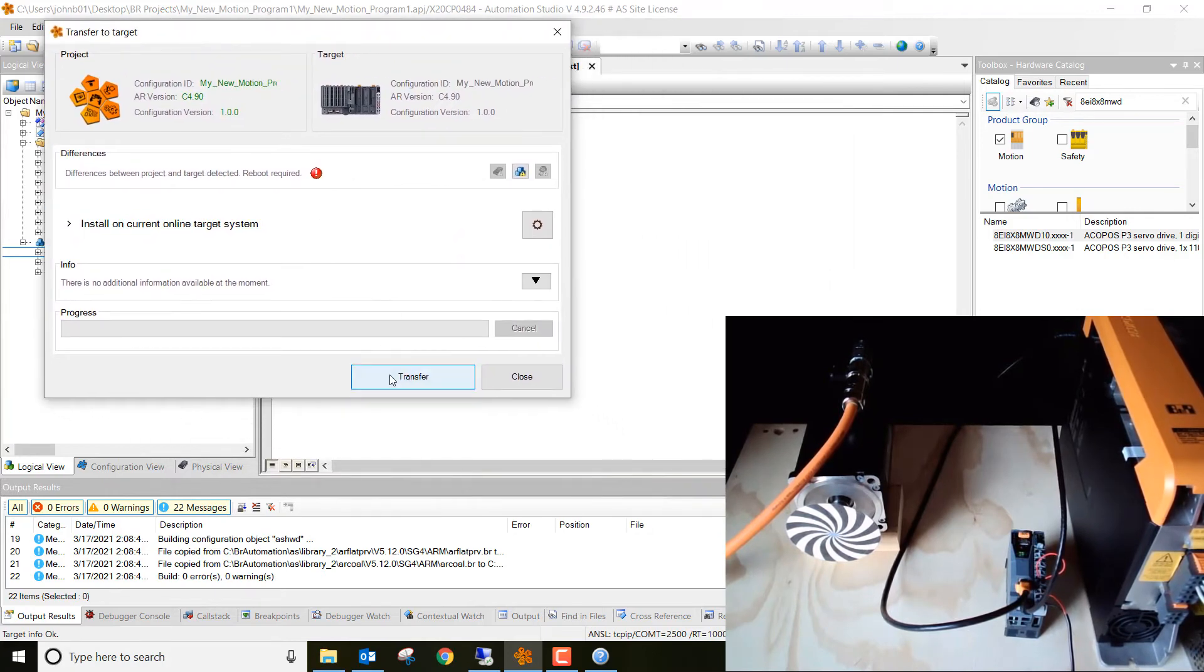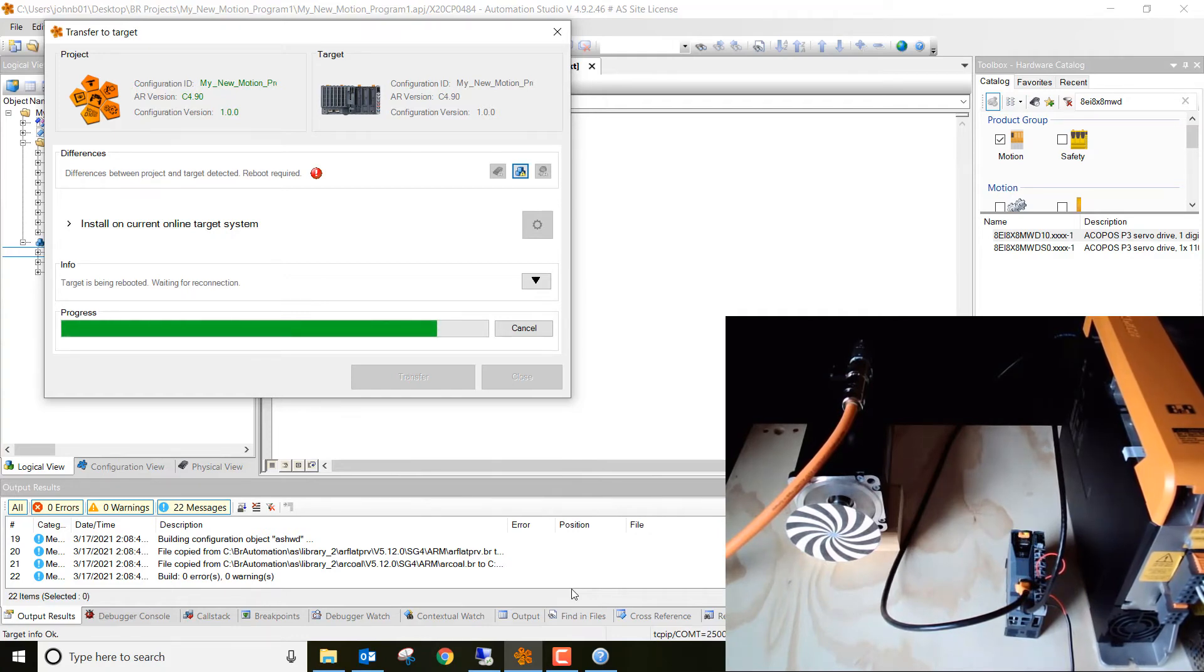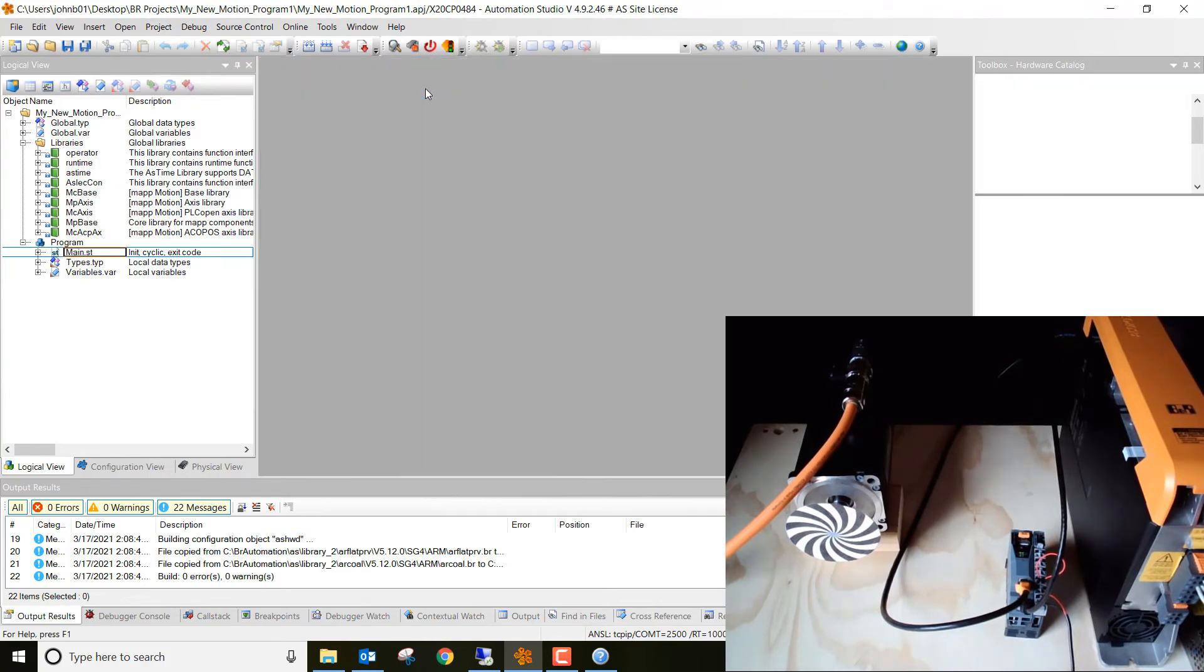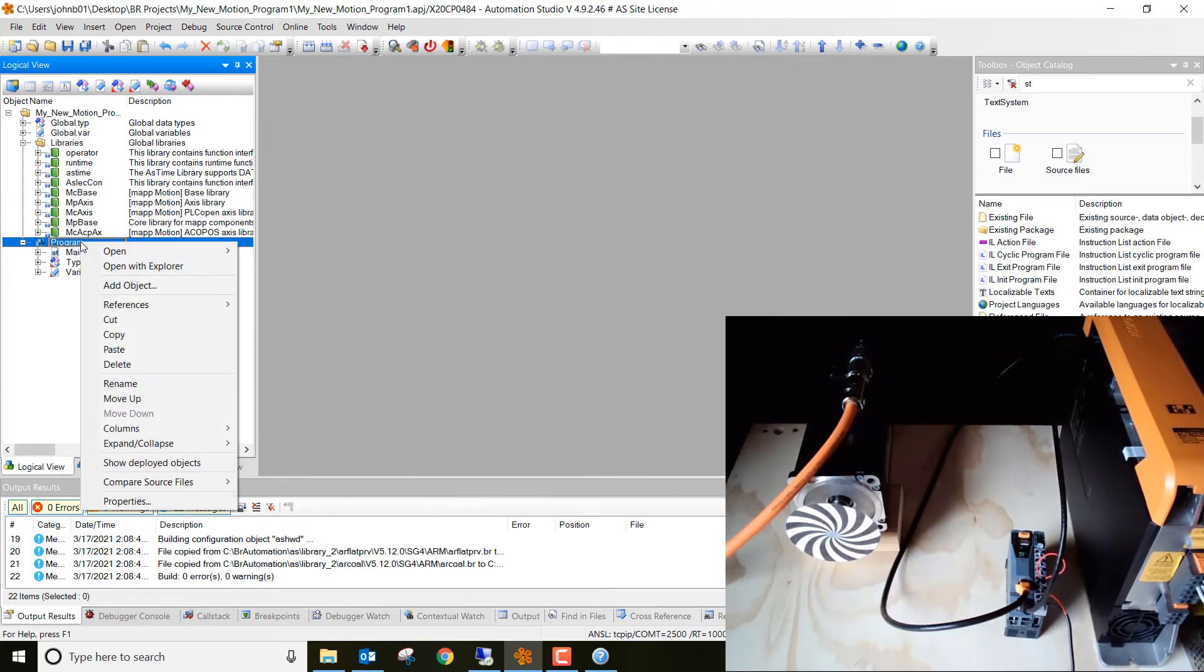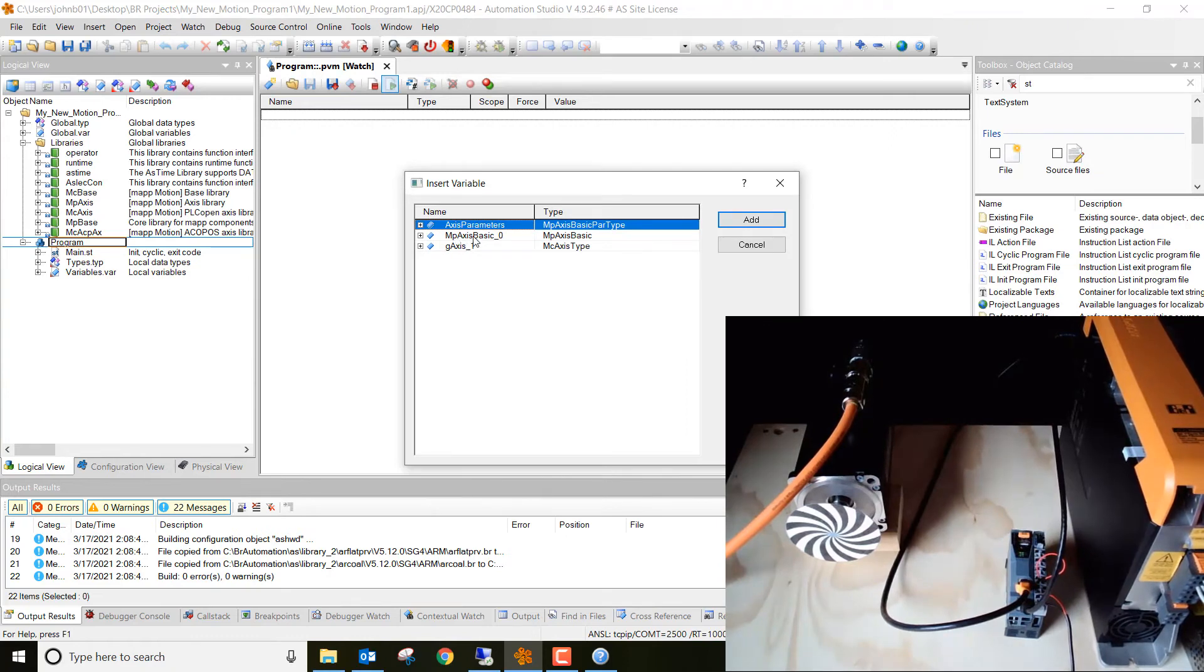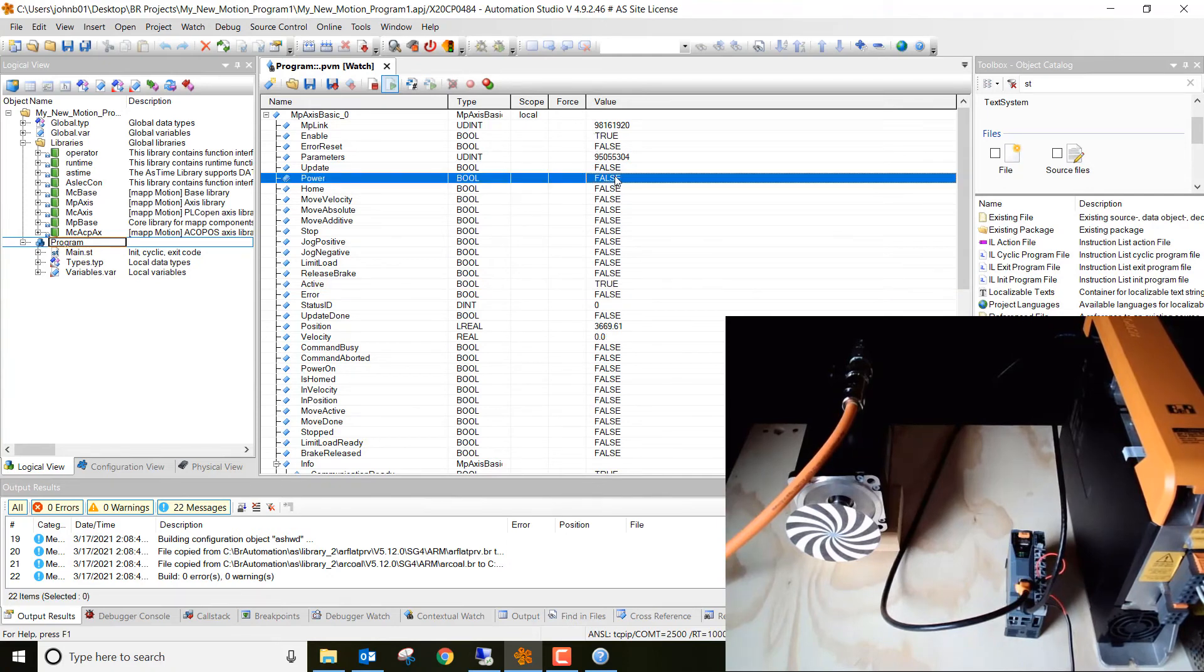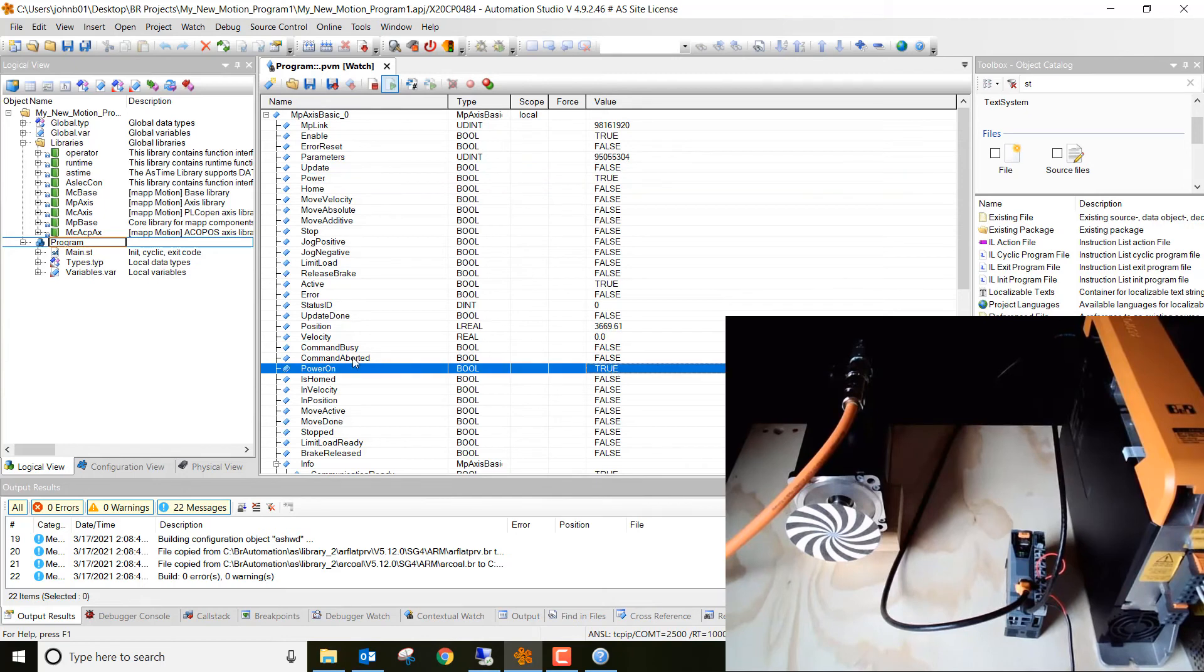Next, what we want to do is go ahead and click transfer. And it's going to actually transfer that project on down to this controller. It's probably going to power it off a couple of times. The drive might turn on and off a few times. That's exactly what you want to see. All right, we're all set. Go ahead and hit close. And then we can close out of these here. And then what we're going to do is highlight over program. Right click on program. Hover over open and then go and hit watch. And then what we want to do is right click in the white space. Insert variable. Go ahead and insert the MP axis basic underscore zero. Click add. All right. So what we want to do is we want to first power this thing on. So we're going to go over here and change it from false to true. So go ahead and click on it. Then hit one for true. And then you'll see right down here power is on. It's true now.